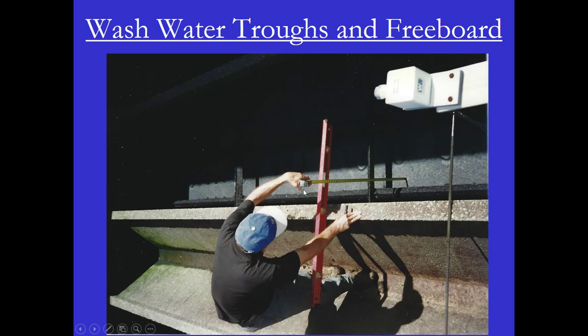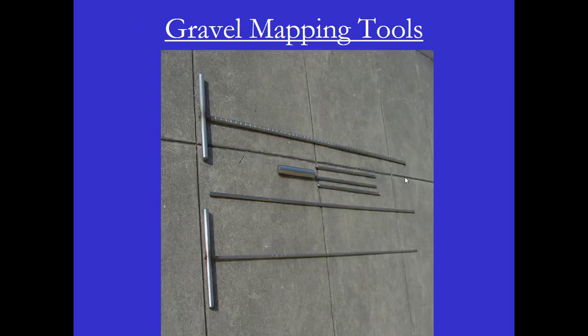The next step is to put the level in the trough and to measure from the bottom of the level, or the top of the wash water trough, down to the filter media. This gives you the freeboard. An important tool for mapping a filter is a gravel mapping tool.